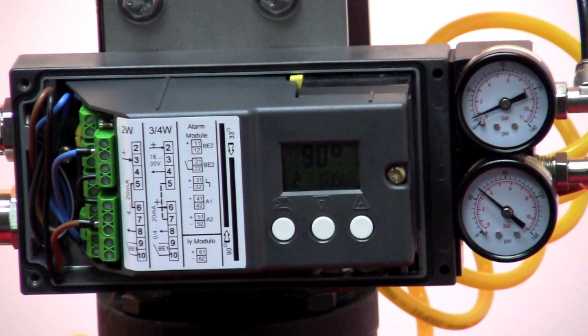And the second thing I need to do is tell the positioner whether I want to operate through a 90 degree rotation of the potentiometer or a 33 degree rotation of the potentiometer. If I select 33 degrees, I take my 32,000 bits of resolution and compress them down into 33 degrees rotation on the pot. I do this for short stroke valves and still get good resolution. Most times, I'm on longer strokes, so I choose 90 degrees rotation.